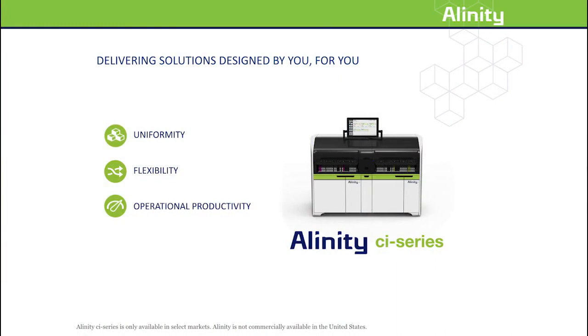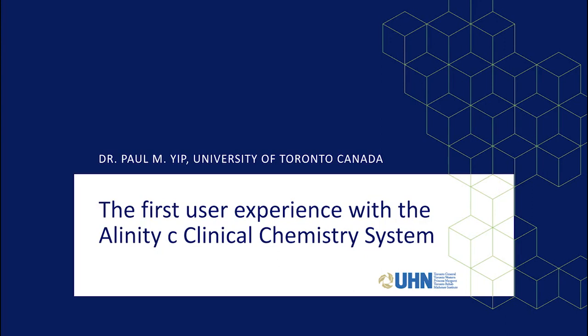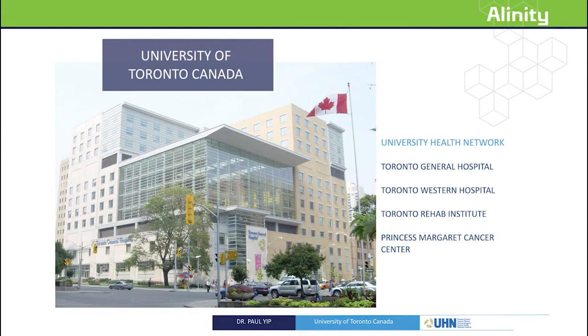We're ready to take our first look at how the Alinity CI series reliability and performance was demonstrated in a core lab in Toronto, Canada. At IFCC 2017 in Athens, we heard Dr. Paul Yip speak. As professor at the University Health Network and University of Toronto, he was one of the first Alinity C clinical chemistry users. He shared his initial experience using the Alinity C system and data gathered on a pre-production system. We installed the Alinity C system in his lab and were able to connect it next to his Architect clinical chemistry system from Abbott, as the Alinity C is just half the size of the Architect. After site qualification, it only took two rounds of performance verification and fairly quick training before Dr. Yip could study the performance of the Alinity C across multiple assays, underscoring the simplicity of the new technology user interface.